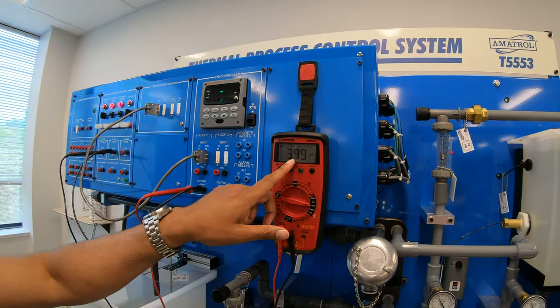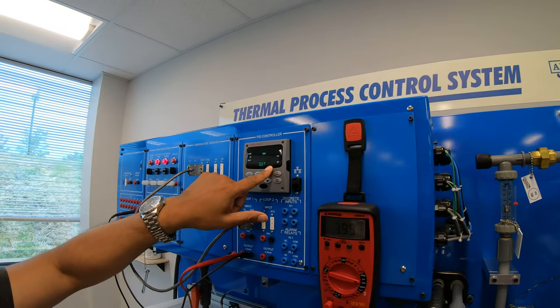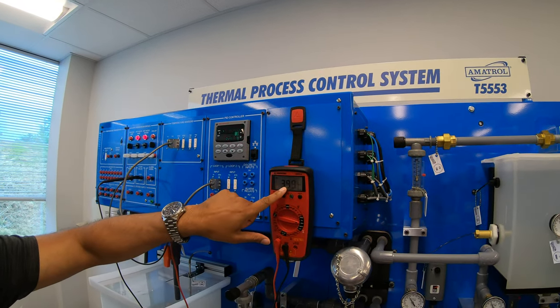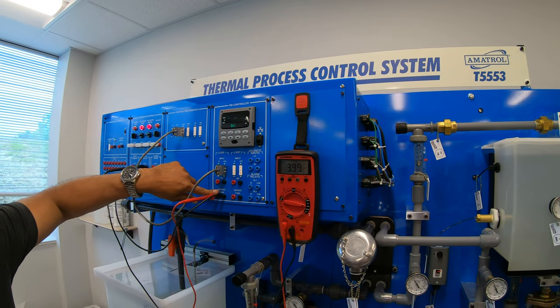So now, as you can see, 4 meters at — zoom out a little bit — at 0. SP means 0%, 4 meters, roughly 3.99, 4 milliamps, which is 4 milliamps here.